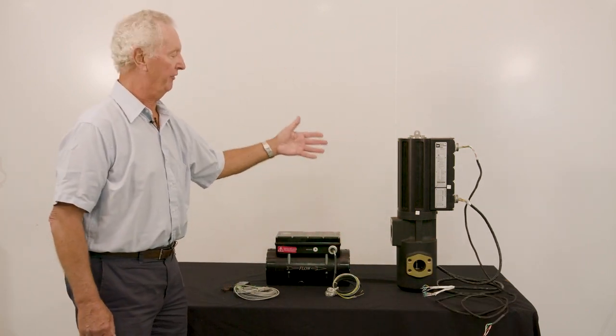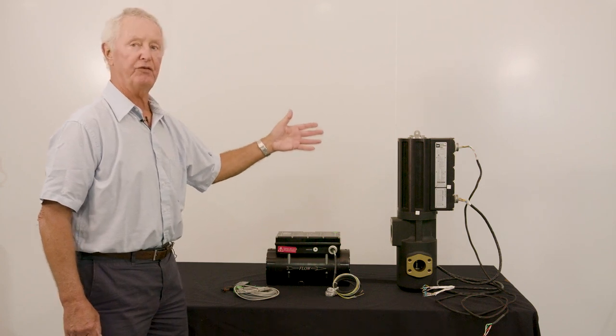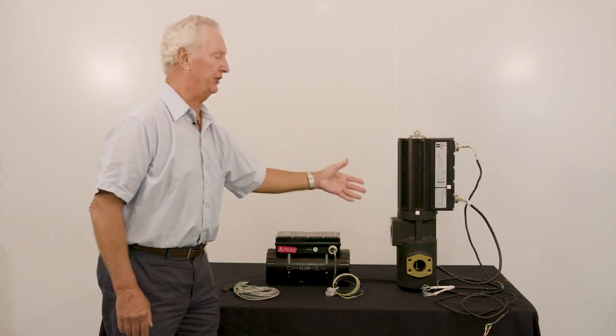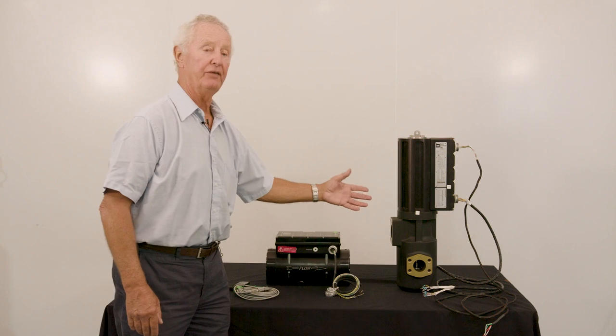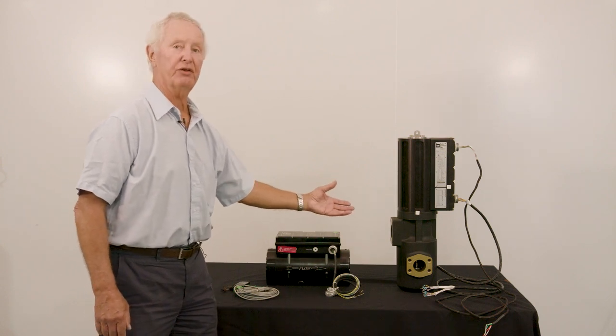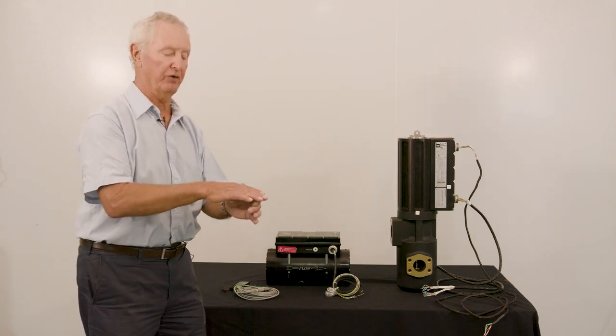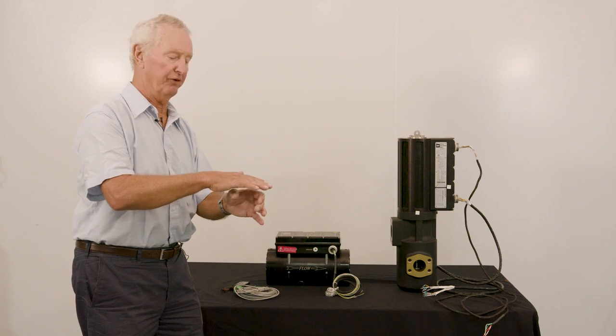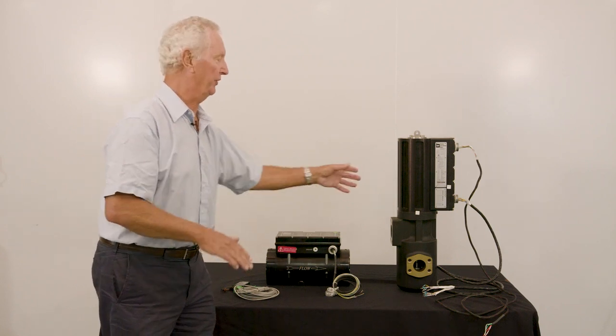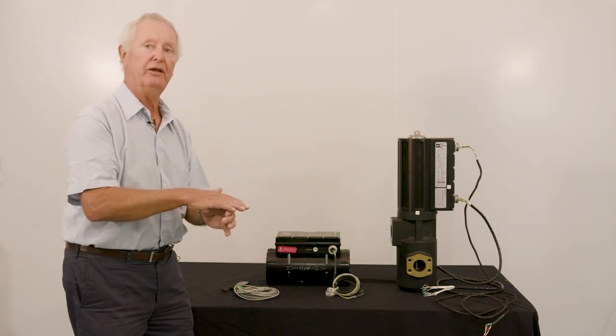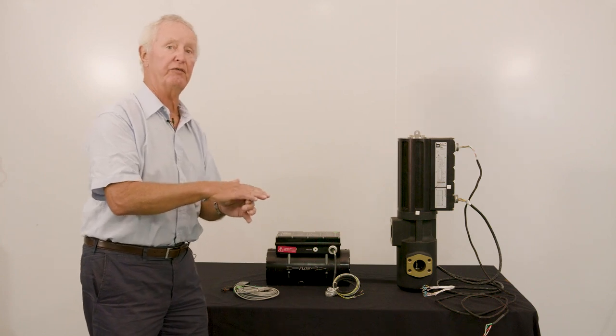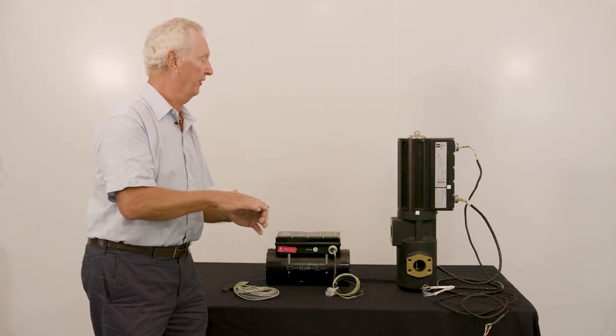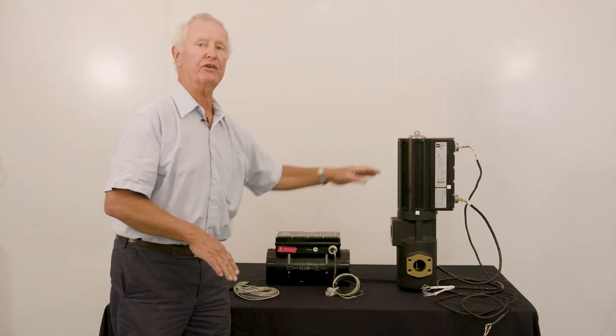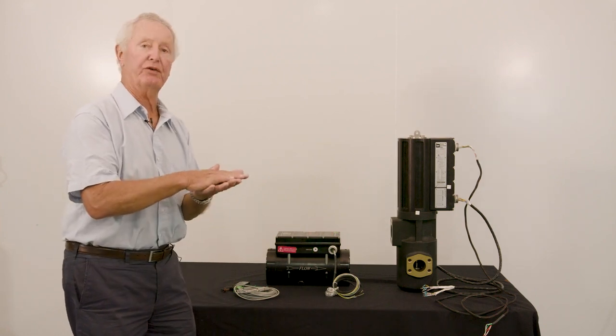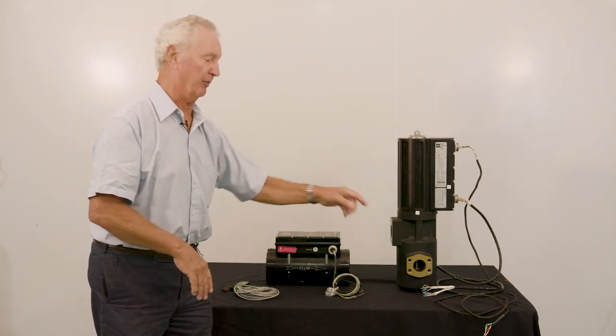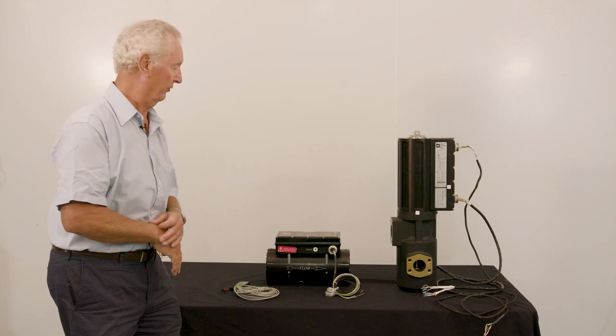These devices have great capability for feedback into computers, so PLCs can precisely control the fuel. The actual control element is rather crude in a way—it's a simple plate over a hole, and it lifts the plate up and down to regulate the fuel. The beauty of it is that it does this with great precision, and it can also be used as a shut-off valve, so it can be completely tight. The drawback is it's very sensitive to dirt because the gaps are very, very small, and another drawback is that it needs 110 volts.